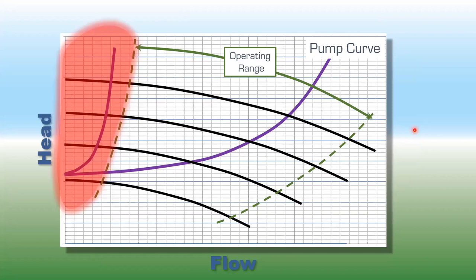If we had done a proper system curve ahead of time, we might have seen the operating point is too far left on a very resistive curve. The solution may be to make the pipe a little larger in diameter or choose a smaller pump. Big pumps are not always better in hydraulic systems — they want to pump large volumes and don't like operating at smaller flows.